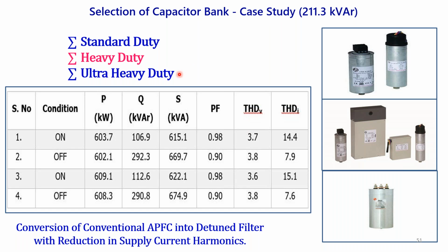So what type of application is required? Based on that, we have to select the capacitors. We did one company during the on-off testing of an APFC. We found that when the capacitor is off, the current harmonic is reduced, whereas when it is on, the capacitor bank is 211.3 kVAr overall. When the capacitor bank is on, the total THD current is going to increase. So that means it is injecting current harmonics.